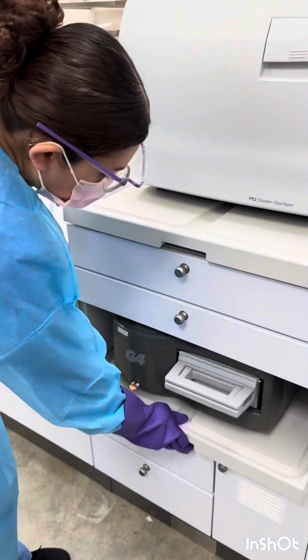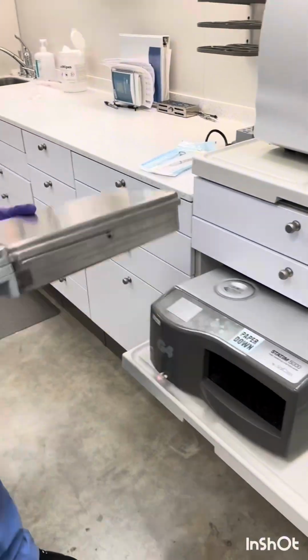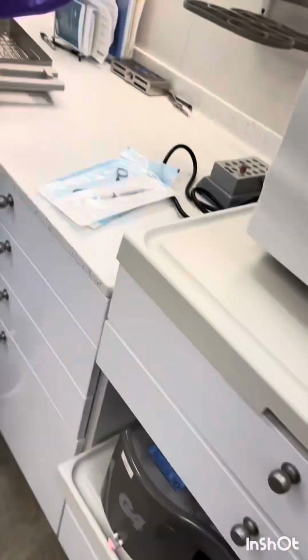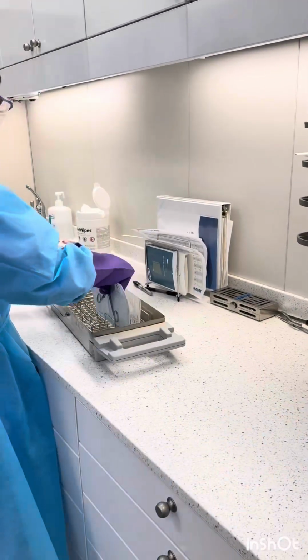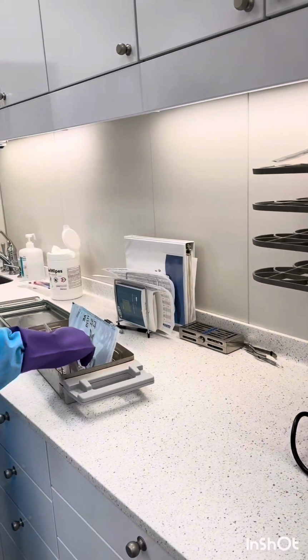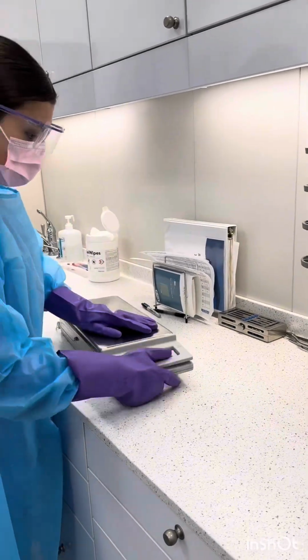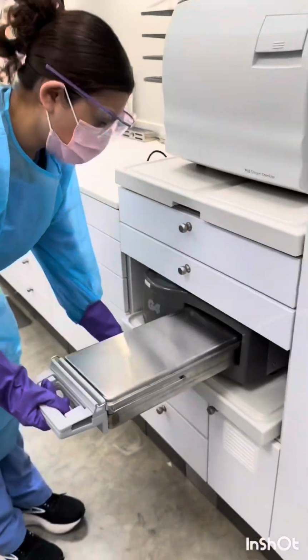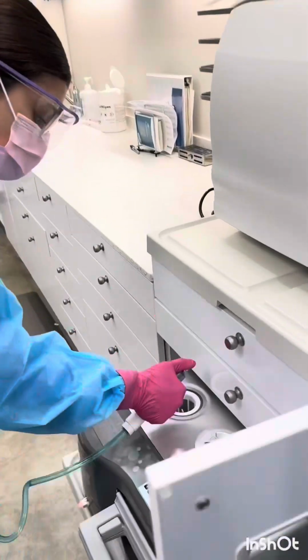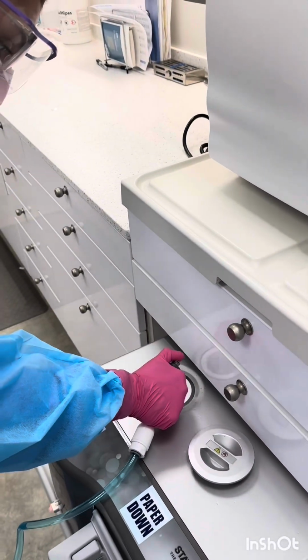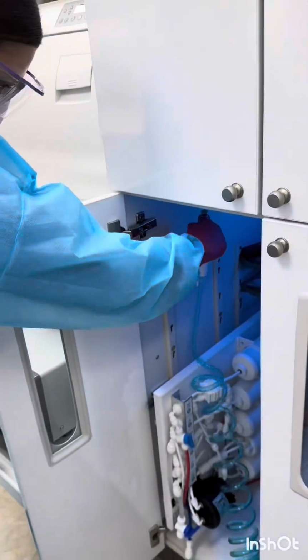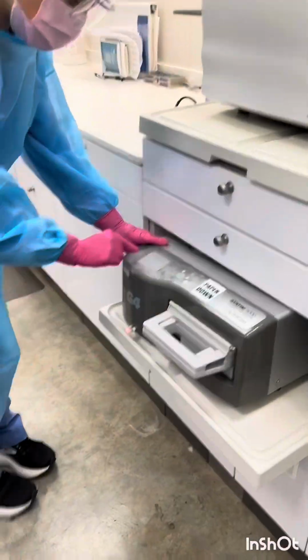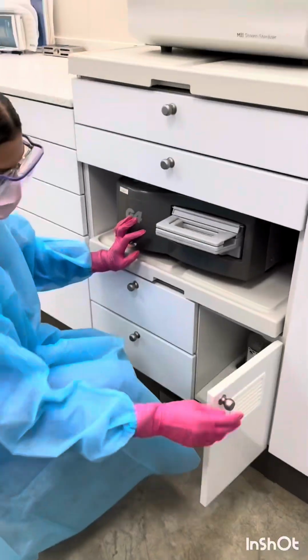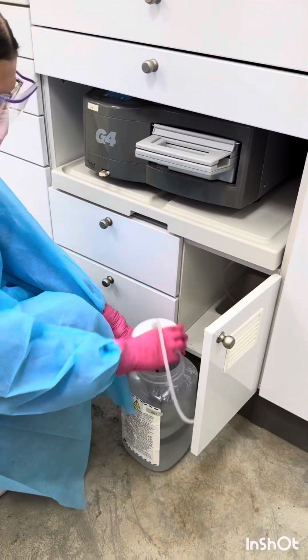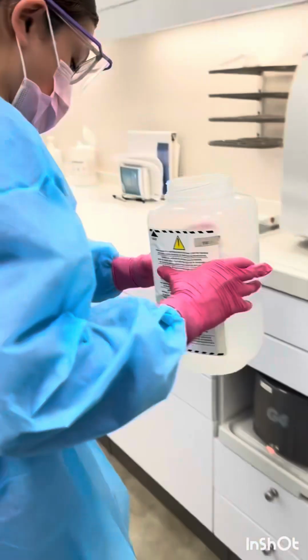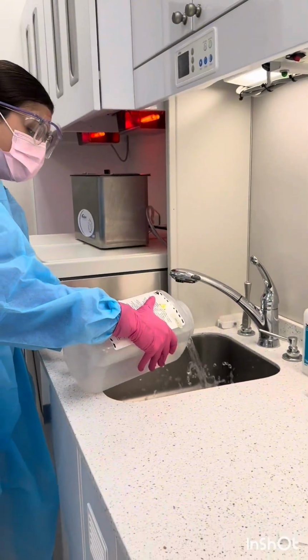We'll now begin loading the Statim, making sure we place everything paper side down. This will run for 14 minutes and it will reach a temperature of 275 degrees. Please make sure that the Statim has enough water while not overfilling it. To start this machine, hit pouches and then start. Before running the machine, make sure the water levels are not too high or low, as this can cause it to overfill and spill or not run properly.